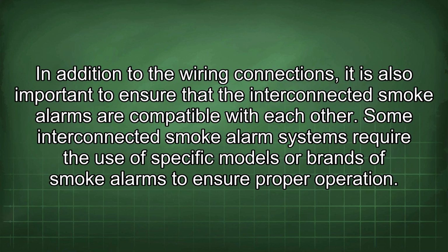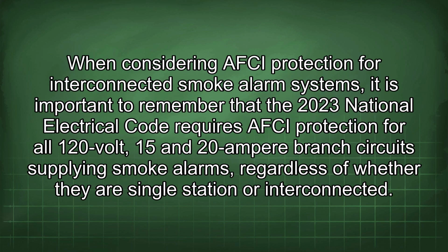properly. In addition to the wiring connections, it is also important to ensure that the interconnected smoke alarms are compatible with each other. Some interconnected smoke alarm systems require the use of specific models or brands of smoke alarms to ensure proper operation. When considering AFCI protection for interconnected smoke alarm systems, it is important to remember that the 2023 National Electrical Code requires AFCI protection for all 120-volt, 15 and 20 ampere branch circuits supplying smoke alarms, regardless of whether they are single station or interconnected.